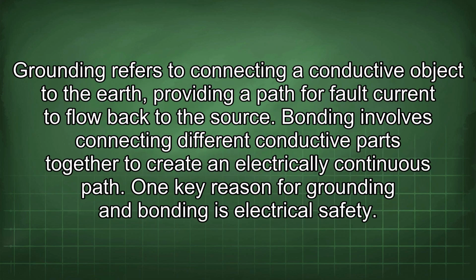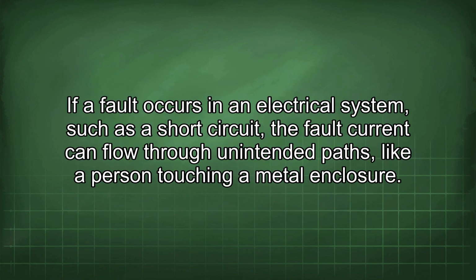Grounding refers to connecting a conductive object to the earth, providing a path for fault current to flow back to the source. Bonding involves connecting different conductive parts together to create an electrically continuous path. One key reason for grounding and bonding is electrical safety. If a fault occurs in an electrical system, such as a short circuit, the fault current can flow through unintended paths, like a person touching a metal enclosure.